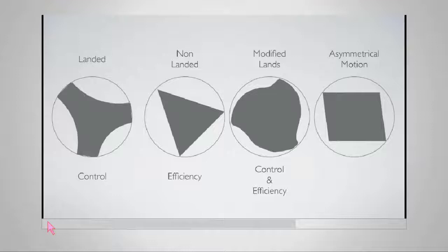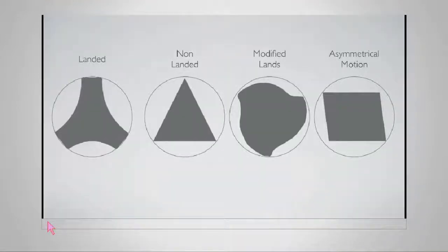Of course, at this point, there was a little dichotomy in terms of motion itself, not so much instrument design. All of these were working in rotational motion. But then suddenly the idea came that part of the problem with rotation is it creates a lot of debris, and people don't do the correct job of reducing their engagement time. They stay in the canal too long. So some manufacturers came and said, well, what can we do? This asymmetrical motion, which is basically cutting and releasing, and the main goal of this motion was to actually have more safety.